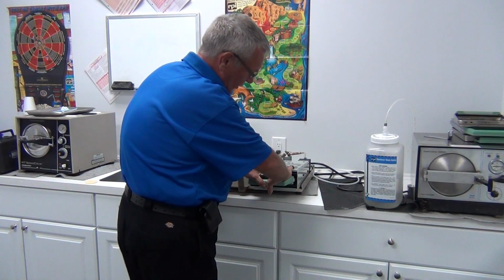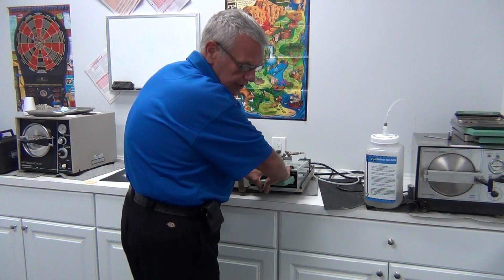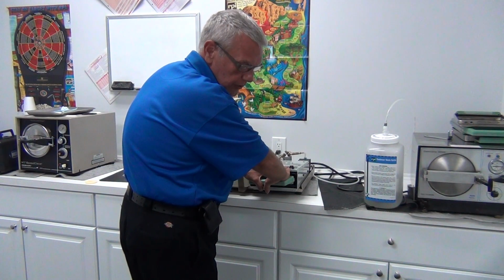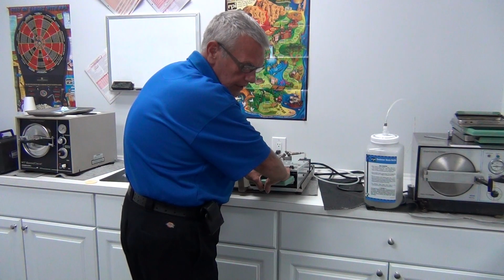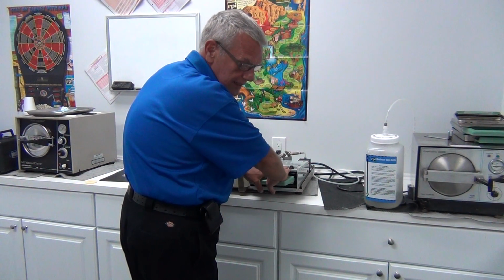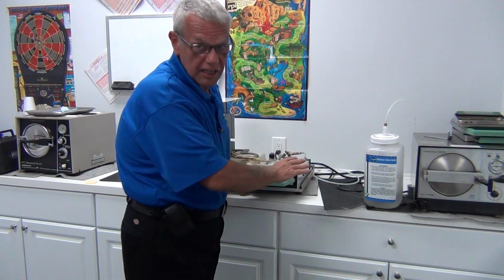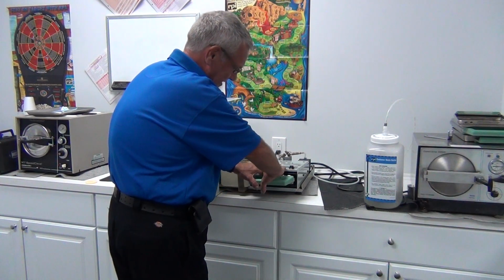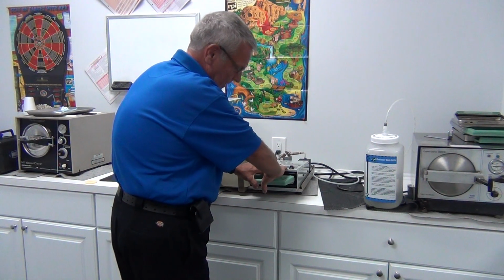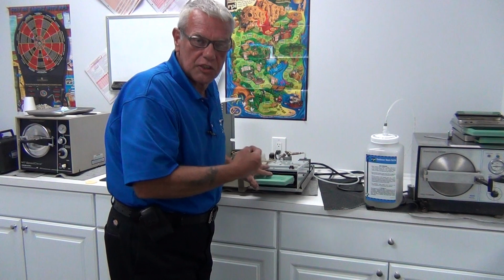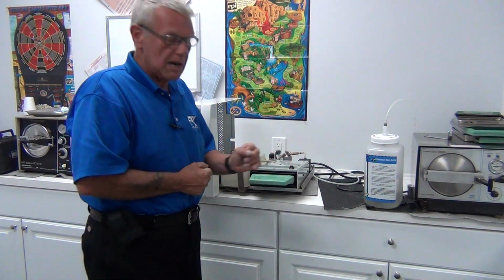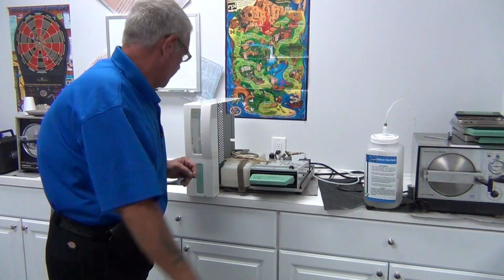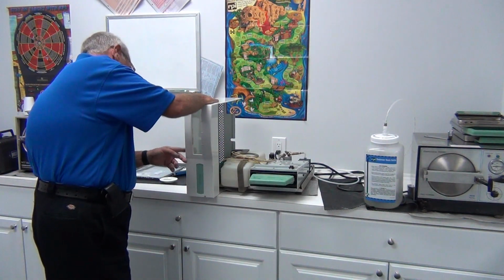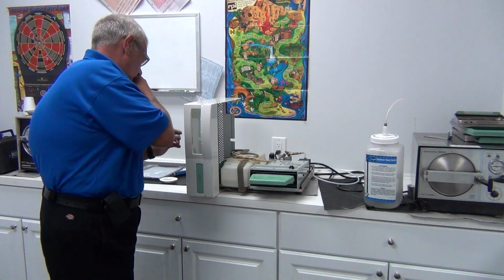We're going to listen for the click, the relays to click in on the machine. I'm going to do it very slowly. Did you hear that? Hear the relays clicking in? That lets you know that the micro switch is engaging the cassette. All systems are go. We're going to select a parameter, unwrapped instruments, and then we'll hit go.